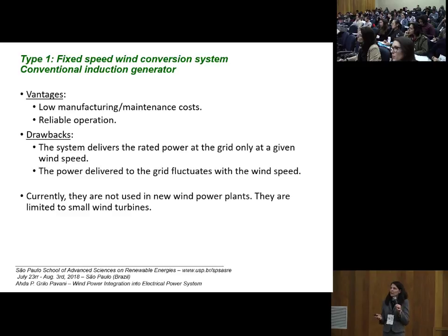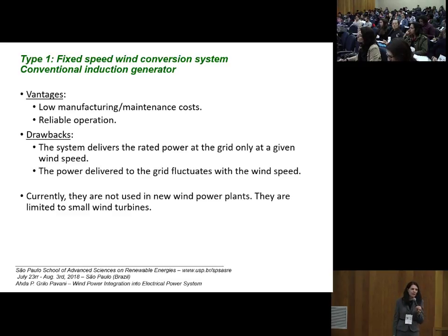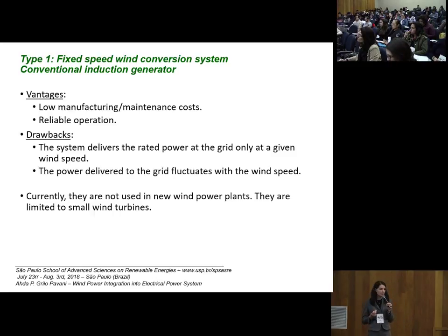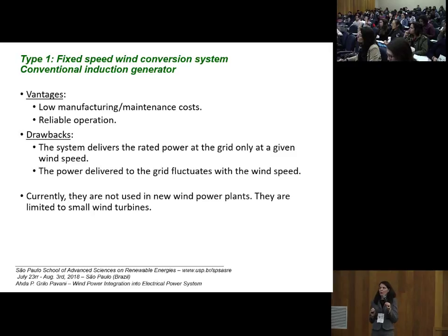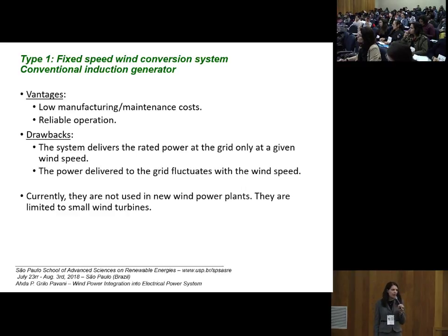The advantages of fixed speed wind conversion systems are low manufacturing and maintenance costs and reliable operation. The drawbacks are that the system delivers rated power only at one specific wind speed, and the power delivered to the grid fluctuates with wind speed, which is a significant problem for power systems. Currently they are not used in new wind power plants and are limited to small or medium-sized wind turbines.